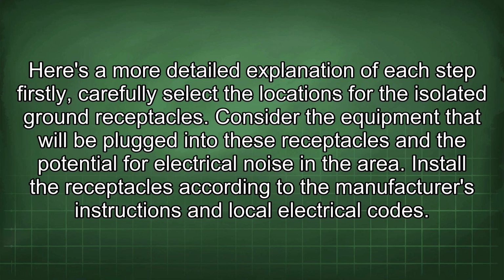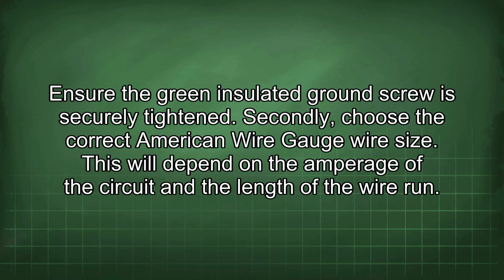Here's a more detailed explanation of each step. Firstly, carefully select the locations for the isolated ground receptacles. Consider the equipment that will be plugged into these receptacles and the potential for electrical noise in the area. Install the receptacles according to the manufacturer's instructions and local electrical codes. Ensure the green insulated ground screw is securely tightened.